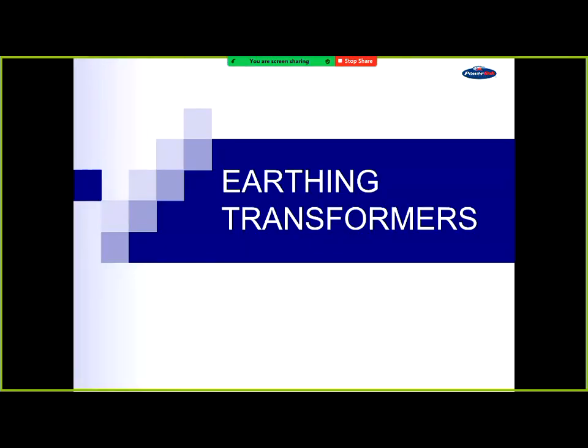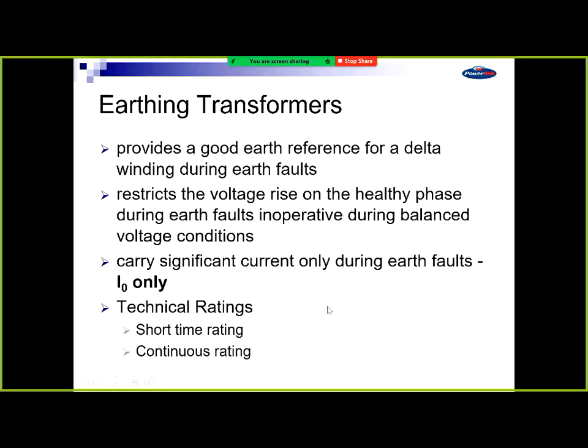Now, looking at an earthing transformer, I'm not sure if you know what an earthing transformer is. So when you get a star-delta connected transformer, the delta doesn't give you any earth fault current. It's actually in isolation in a zero sequence network. So to get earth fault current, you need an earthing transformer. They'll also keep the voltages down when you've got earth faults.